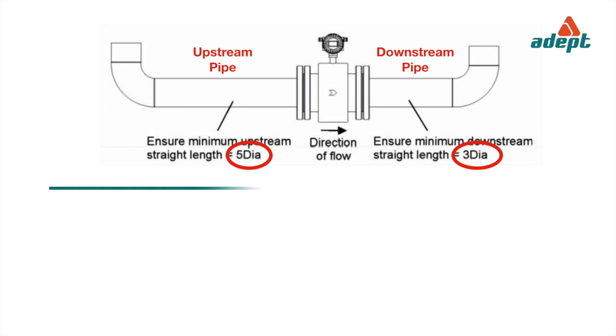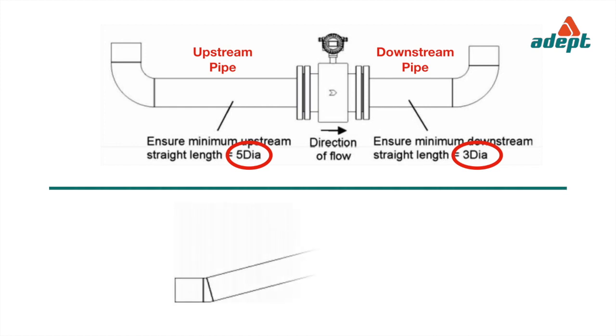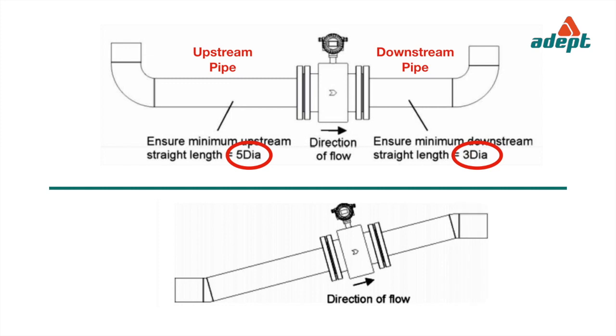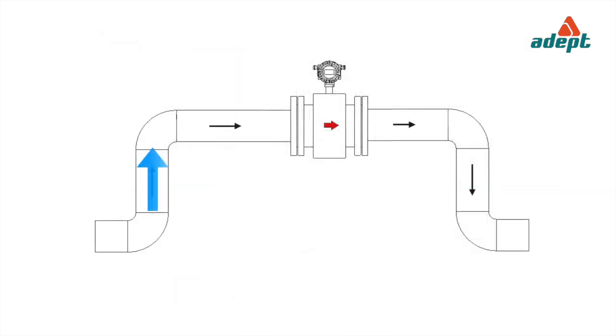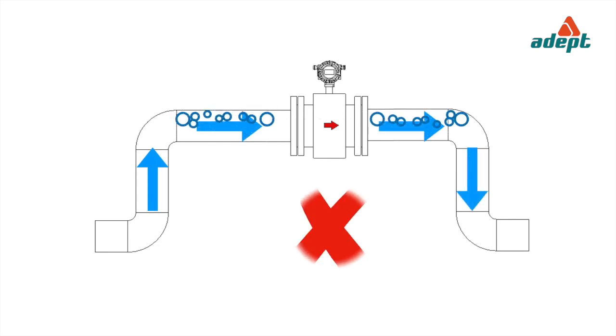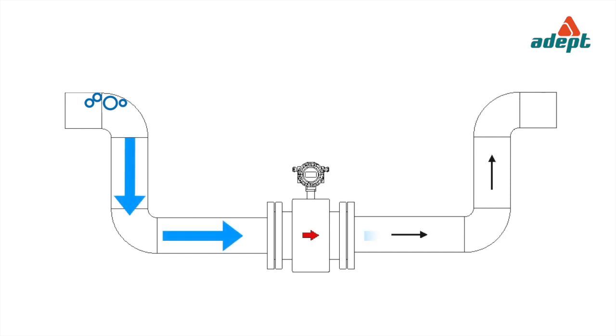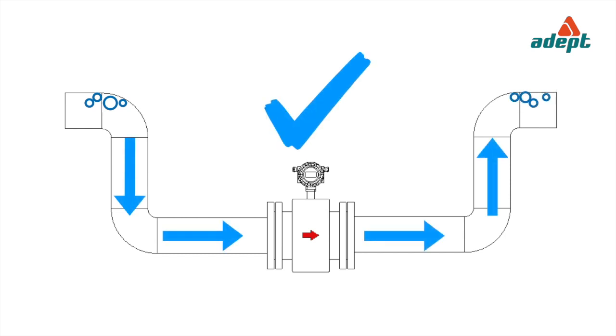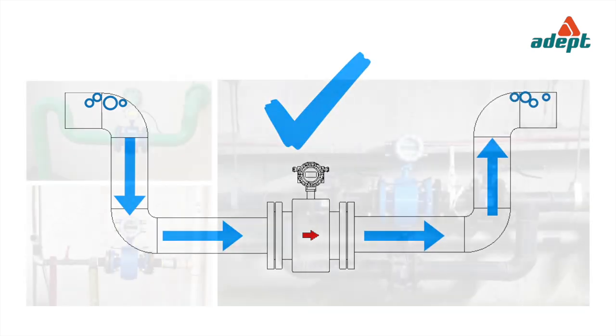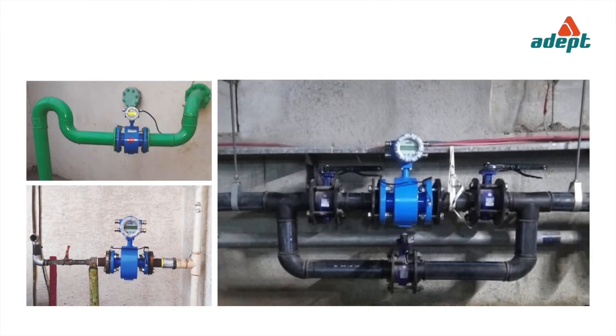The flow tube may be installed in horizontal pipelines, preferably with a slight upward gradient in the direction of the flow. The piping layout must prevent any build-up of air. Any entrained air should be carried out of the flow tube by the liquid flow. Ensure that the installation location is such that water or moisture does not enter the electrical termination area.